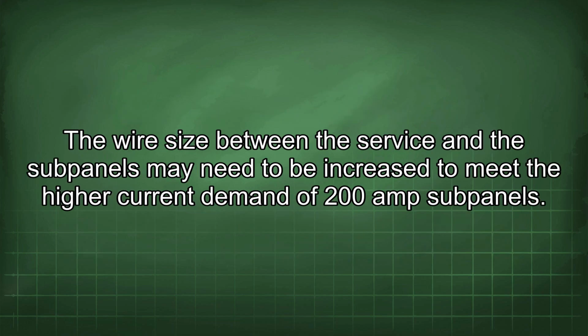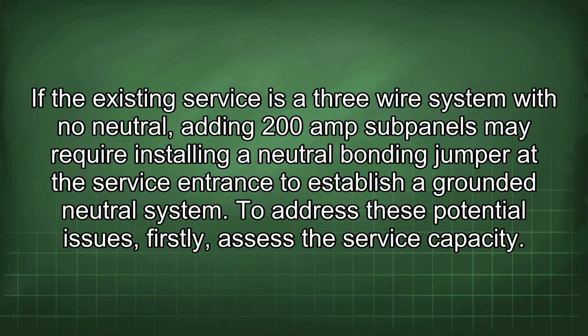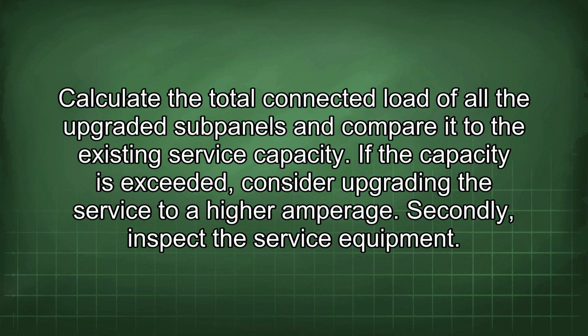The wire size between the service and the subpanels may need to be increased to meet the higher current demand of 200 amp subpanels. If the existing service is a 3-wire system with no neutral, adding 200 amp subpanels may require installing a neutral bonding jumper at the service entrance to establish a grounded neutral system. To address these potential issues, firstly assess the service capacity. Calculate the total connected load of all the upgraded subpanels and compare it to the existing service capacity. If the capacity is exceeded, consider upgrading the service to a higher amperage.